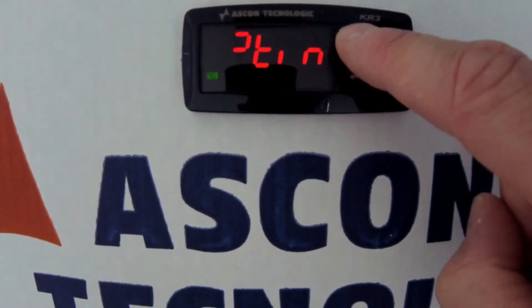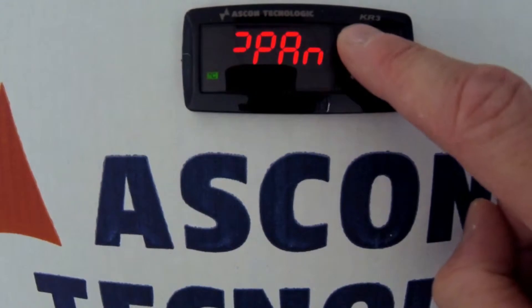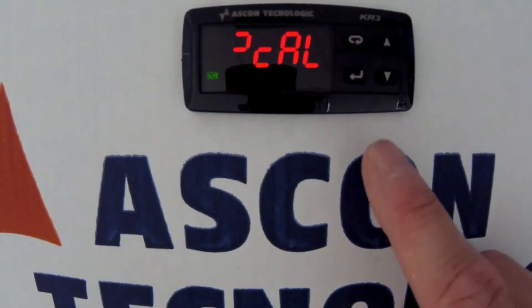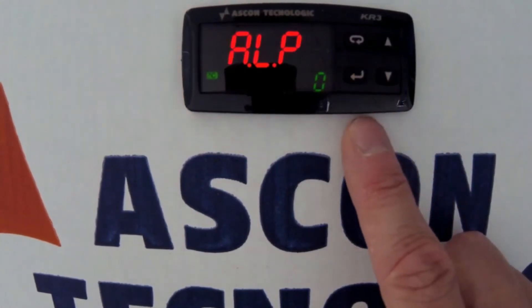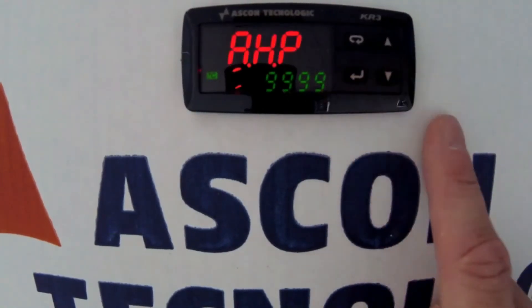In this group there are just four parameters. We need to change ALP and AHP both to 5 degrees. Scroll around using the enter key. Use up to set in 5 and enter again to move on.